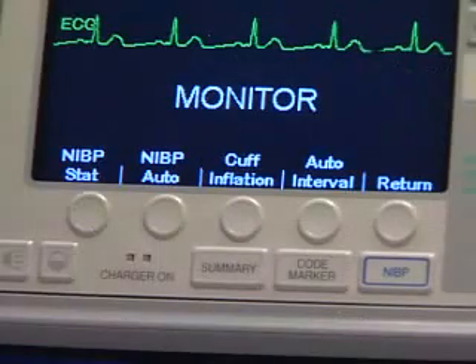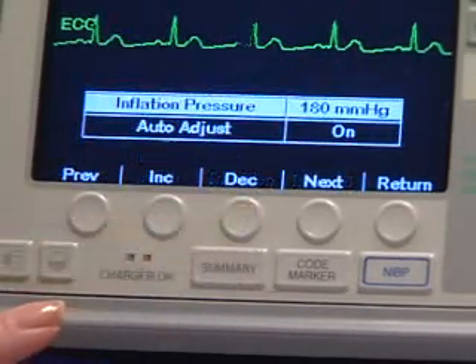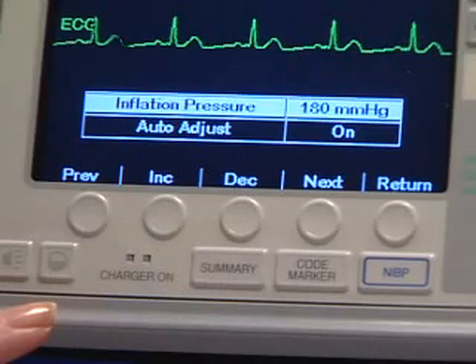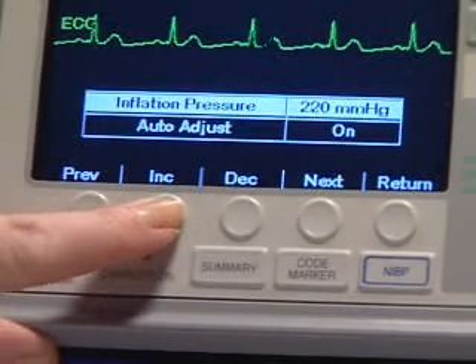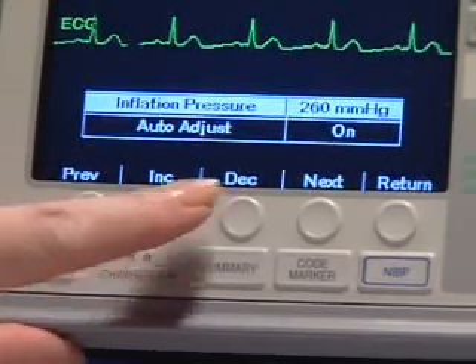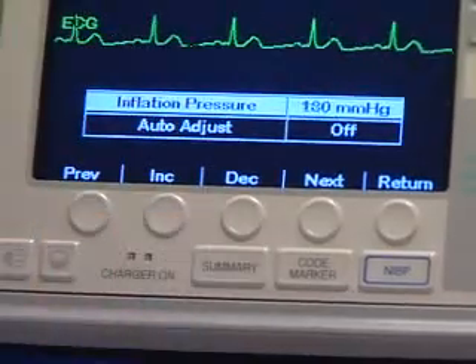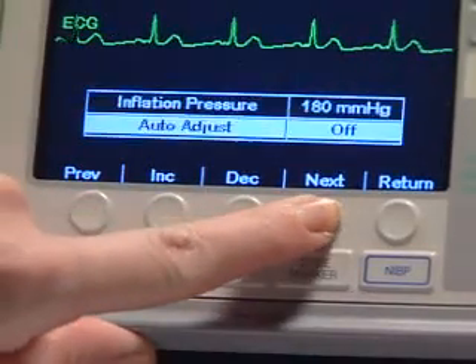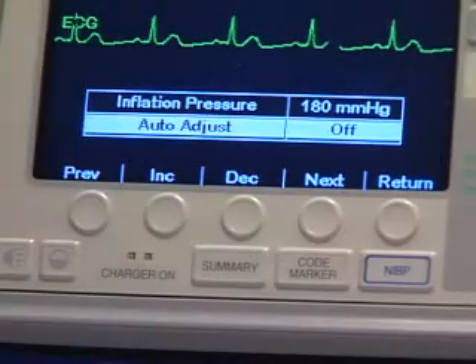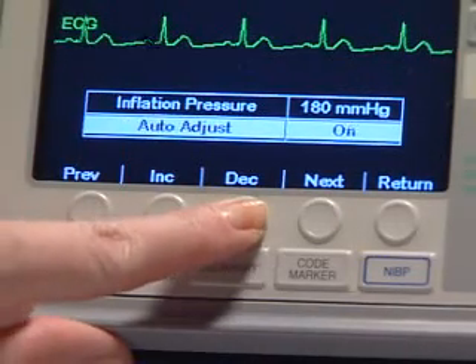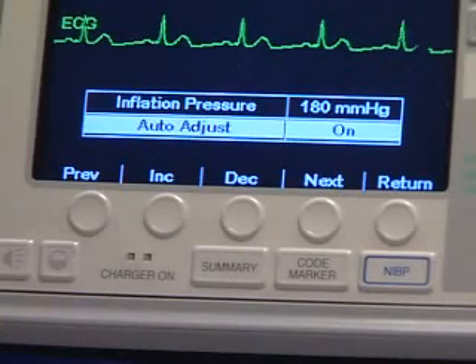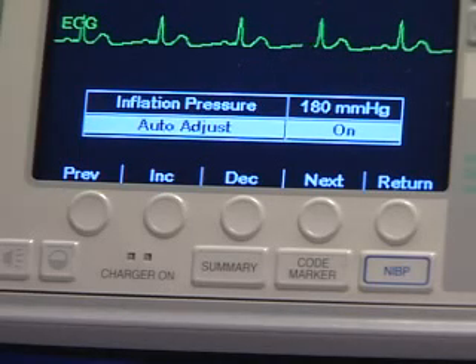Before taking a measurement, check that the initial cuff inflation pressure is appropriate for your patient. The default cuff inflation pressure is 180 millimeters of mercury. To adjust the inflation pressure, press the cuff inflation soft key, and then press the Increase or Decrease keys. If the Auto Adjust feature is set to off, the selected cuff inflation pressure will be used for all measurements. If the Auto Adjust feature is set to on, the selected cuff inflation pressure is used for only that first measurement. After that first measurement, the cuff inflation pressure automatically adjusts to 30 millimeters of mercury greater than the systolic value of the previous measurement.